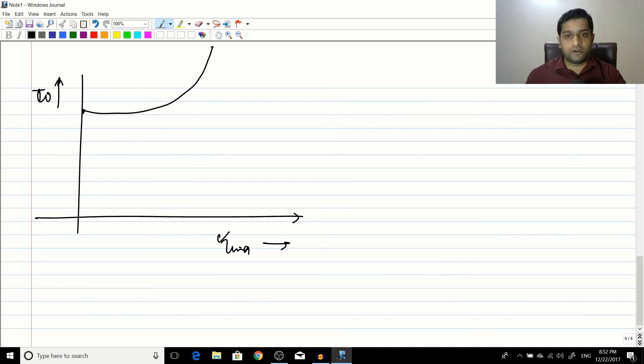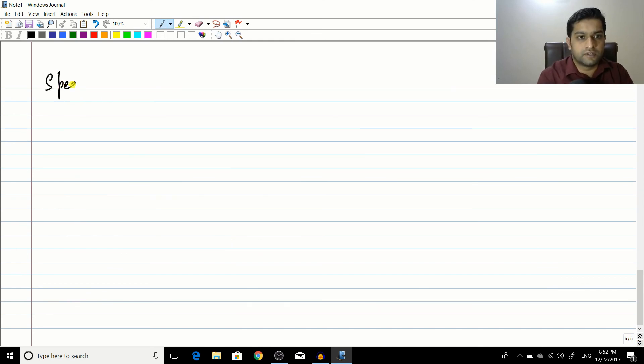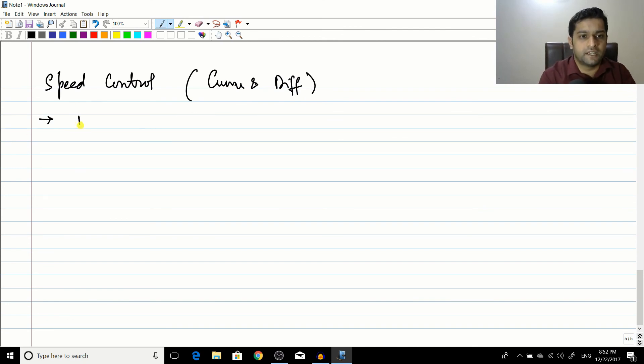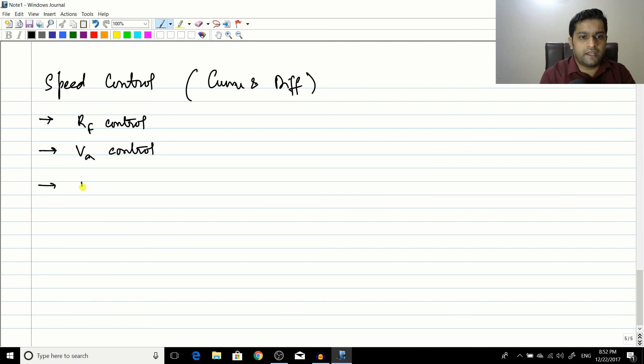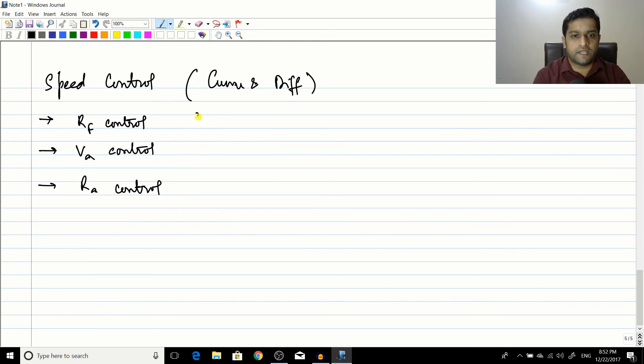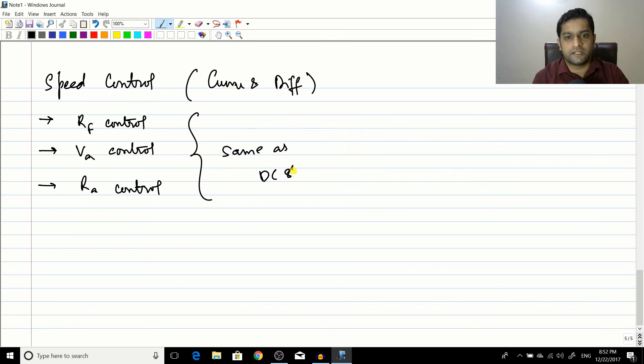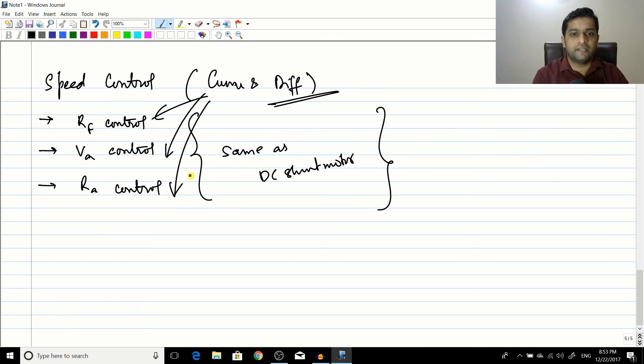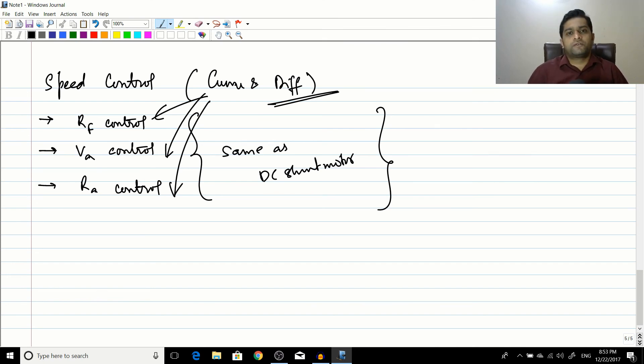For speed control of both cumulative and differential compound motors, the same three methods used for the shunt motor apply: field resistance control (Rf), armature voltage control (Va), and armature resistance control (Ra). The characteristics are exactly the same as the DC shunt motor. Since differentially compound motors are not used practically, the discussion mainly applies to the cumulatively compound motor.